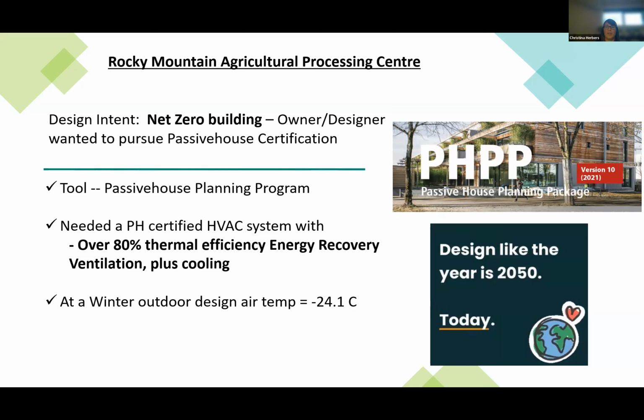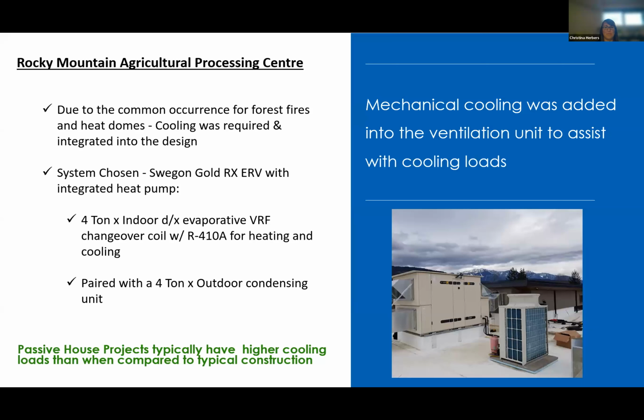So I just put this little blurb here: design like the year's 2050. Let's start designing for that today. Why wait until things potentially get worse? So initially we were just talking about ventilation with the ERV. And then as we looked into it more and more, we realized, or Kevin was stating, that forest fires and heat domes are getting to be very common. And in Passive House buildings, they typically have a higher cooling load compared to typical construction, again because of that air tightness, and whatever heat is created in the building seems to stay in the building. So the chosen system was a Swegon Gold RX ERV with an integrated heat pump.